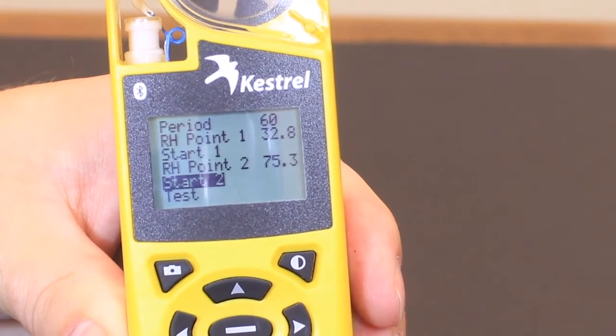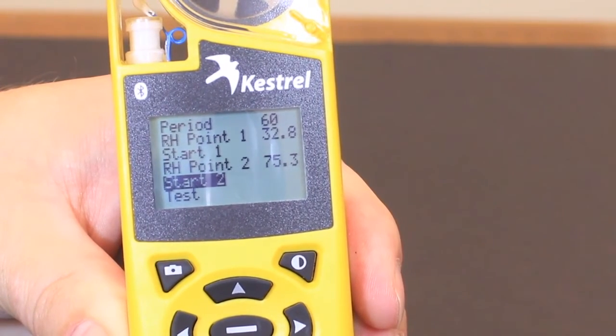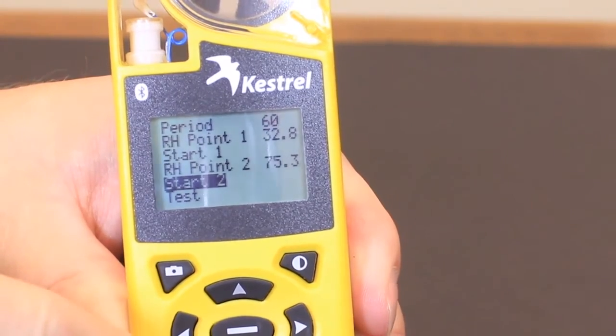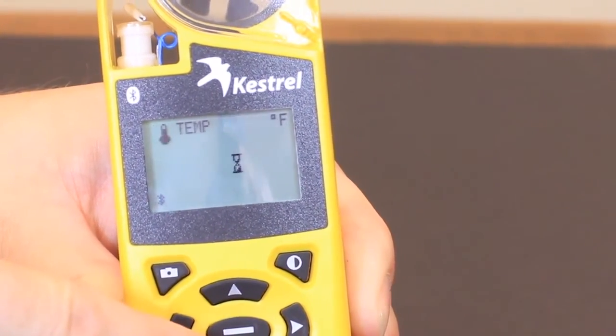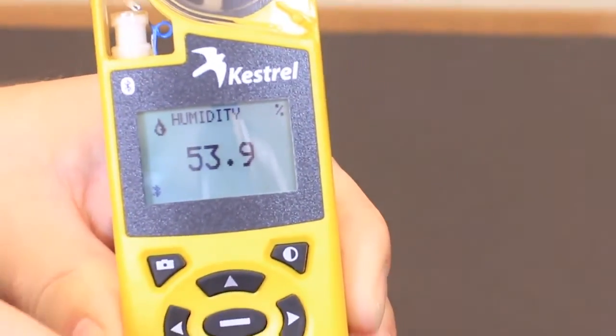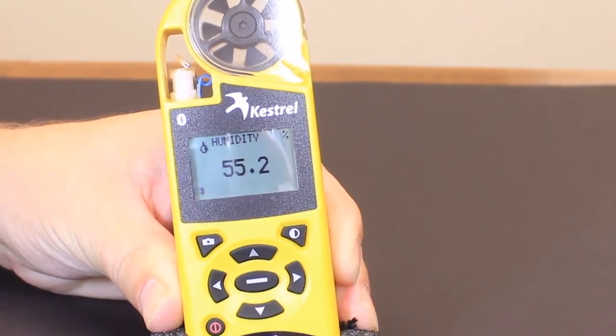Now we pulled it from the second calibration chamber. The humidity has been calibrated and we can hit the power button to get back to the main menu and notice that our humidity is now within spec again.